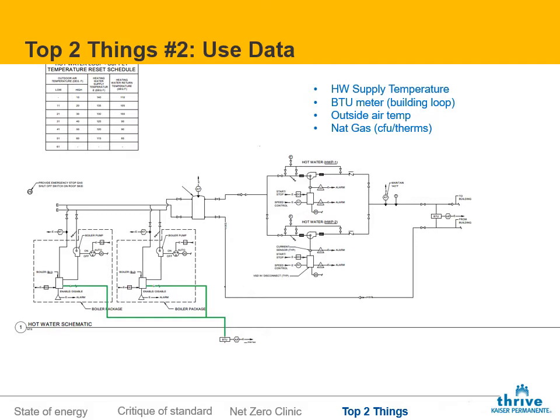And let's talk through this as an example. I've highlighted really just a very few DDC points here, right? Supply water temperature, the BTU meter, which could be a GPM meter. In this case, it's a BTU meter. Then a natural gas meter and an outside air temperature. You also would want to have a return water temperature sensor on this thing. But let's imagine at the end of construction, we're going to trend about 5 points for 5 business days at 15-minute intervals. So we're going to get a spreadsheet from the control system that has just a very few number of columns to it, right?